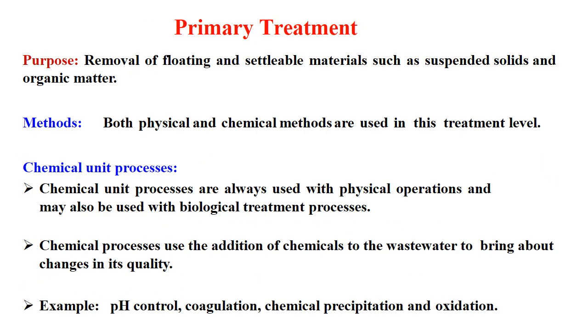In primary treatment, the purpose is removal of floating and settleable materials such as suspended solids and organic matter. Both physical and chemical methods are used. Chemical unit processes are always used with physical operations and may also be used with biological treatment. Chemical processes involve the addition of chemicals to wastewater to bring about changes in its quality — examples include pH control, coagulation, chemical precipitation, and oxidation.